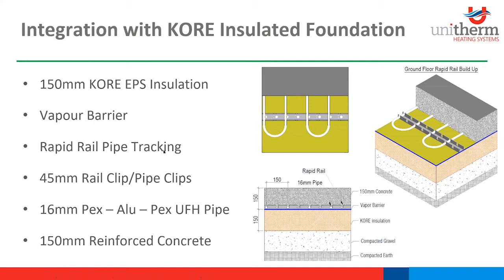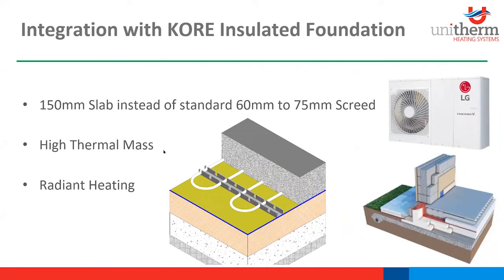So this is basically our thermal mass that we're talking about. Instead of going concrete, insulation, screed, we're going just insulation, concrete slab, our thermal mass and screed in one. With twice the thermal mass here, we're looking at getting out twice the radiation. As mentioned previously, for a 75 mil screed, the method of heat transfer from the heated floor is about 55% radiation and 45% convection. But with a 150 mil slab, we've doubled the thermal mass in the floor. So we've significantly increased the longevity of radiation from the floor. And because the majority of the heat is now predominantly radiant, it creates occupant thermal comfort at even lower air temperatures. That's a big thing with radiant heating. You don't need to have it up at 21, 22 degrees to get that thermal comfort. Even at 18, 19 degrees, the more radiant the heat is, the more you feel it on your body.